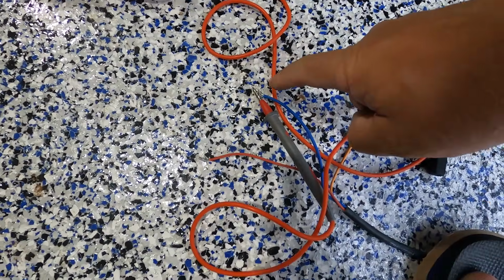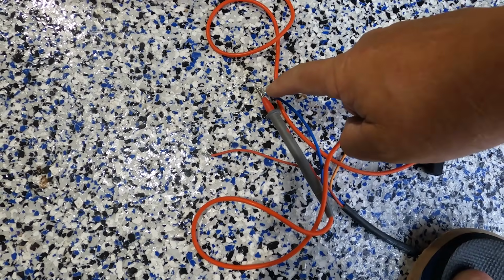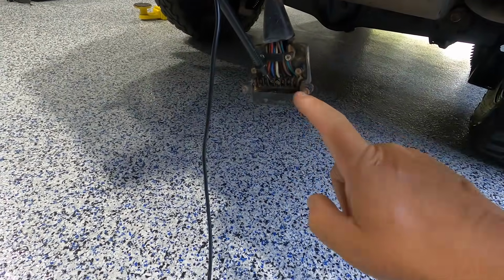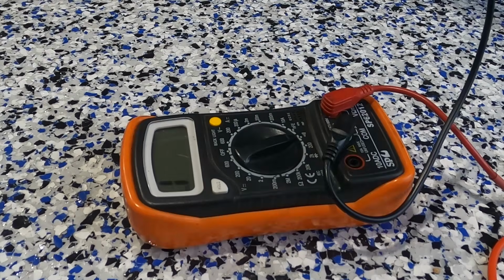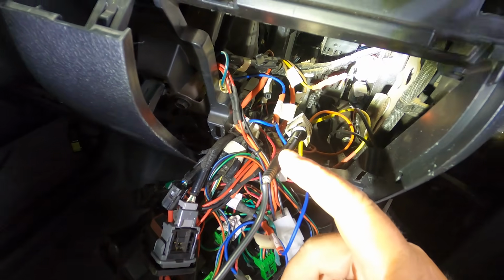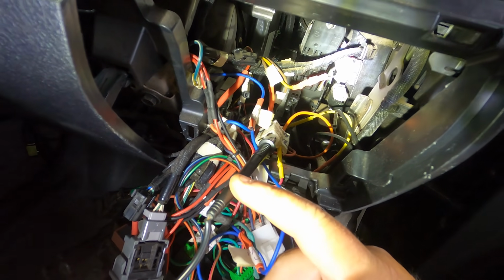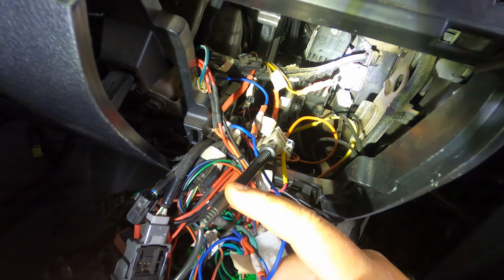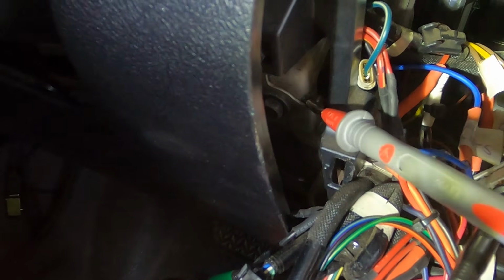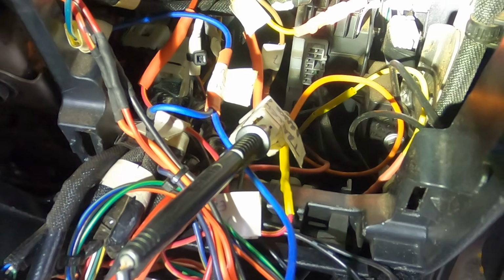Now I'll do the same for the blue wire. That's hooked up to one end of my ohm meter, trailer plug at the other end. Let me connect this blue wire up. Excellent, continuity. Now I've got my probe on the white wire in that plug, which is the earth, and there's a bit of steel here in the dash structure — I'll take this end of the probe there. Beautiful, three out of four wires confirmed hooked up correctly.